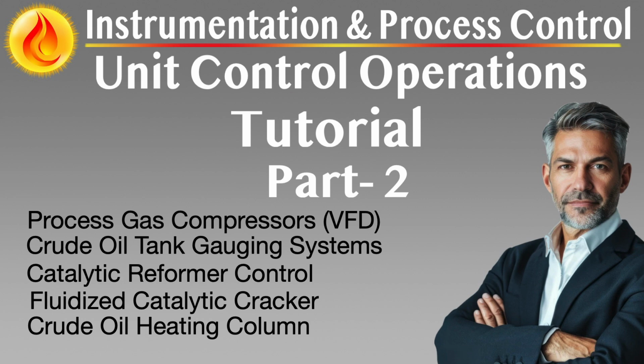Process integration often necessitates coordination between multiple compressors, headers, or trains. In such configurations, master-follower VFD arrangements or centralized control strategies balance load across units to ensure efficient capacity utilization. These controllers optimize power distribution, reduce interstage backflow, and allow seamless handover between parallel units. Combined with real-time monitoring of suction header pressure and gas quality, these strategies improve stability and avoid hunting or flow instability at lower pressures.